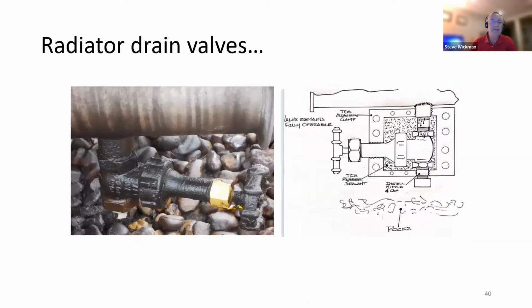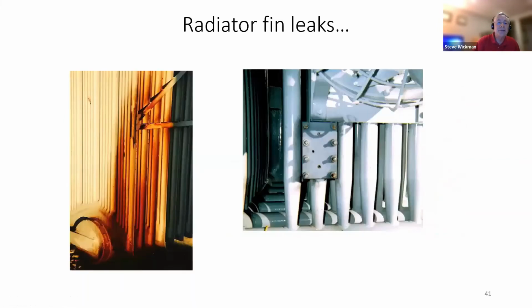Radiator drain valves are kind of a nuisance situation, as I term it here. They can develop leaks and make a nice gooey mess in your drain rock. We can fabricate a clamp out of just a little aluminum box to go around that, and put an extension on the drain side to allow you to continue to use that valve as designed. All you have to do is enclose around that valve stem area and make it tight enough that the oil isn't going to infiltrate out. Of course, it's filled with the sealant, so you're going to effectively contain those leaks.